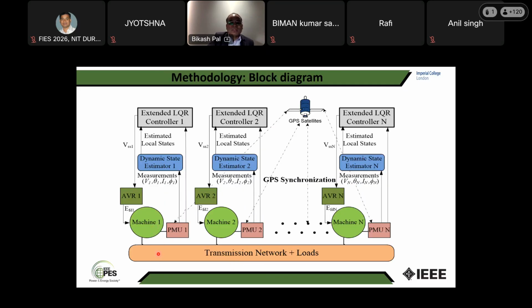So this is your machine, this is your network, machine and network. So represent the whole of the eastern region grid in India by this transmission. Now there is only one grid, so you can represent the whole of the India grid like this and put every power plant as an interface. They have PMUs, and GPS gives you the timestamp. So this voltage and current, this voltage and current, are all being sampled at the same time all over the network. Then these measurements, pseudo input V, theta, I, phi, go to the estimator and you estimate the state. This also brings the timing, and then you have the control output. It comes to the automatic voltage regulator of the generator and then it does that.